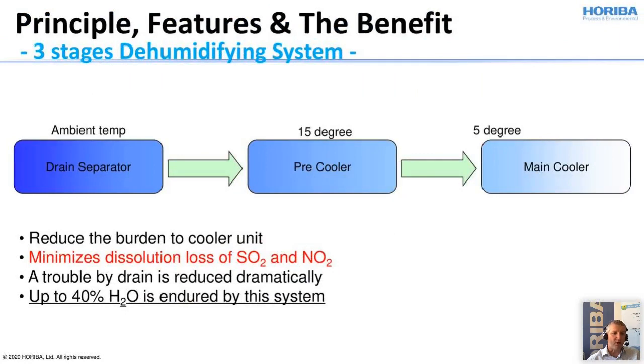Just one topic I want to point out, the three-stage dehumidifying system. First of all, we cool down the gas with a drain separator at ambient temp. At 15 degrees, we have a pre-cooler. And finally, we have a main cooler, which reduces the gas to a 5 degrees C humidity level. This minimizes the dissolution loss of the SO2 and the NO2, and the trouble caused by the drain in the gas is reduced dramatically. With this solution, we can handle humidity levels up to 40% relative humidity in the sample gas.